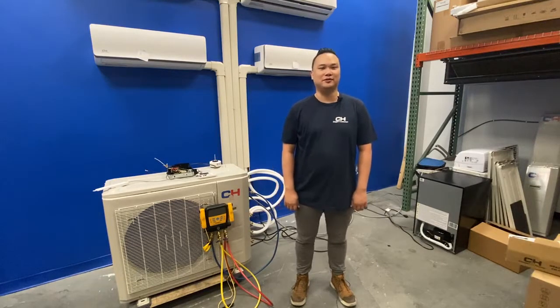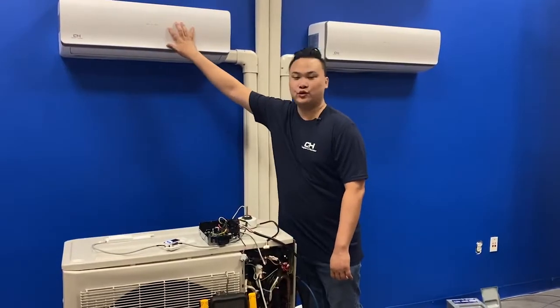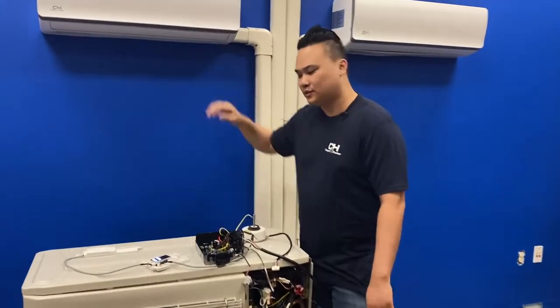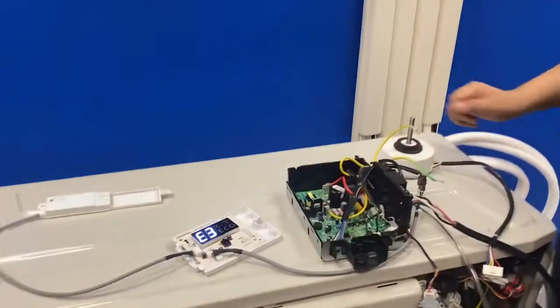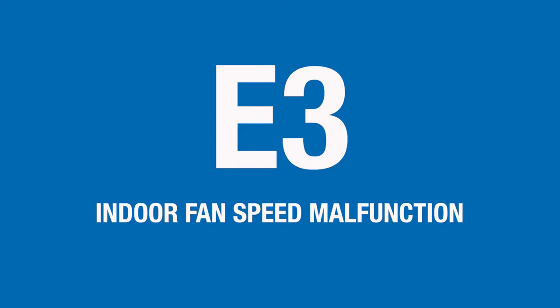Today we're going to go over some error codes. The error code will show on the front of your unit. For simulation, I have it here already. If your indoor unit is displaying an E3 error code, that indicates an indoor fan motor malfunction.